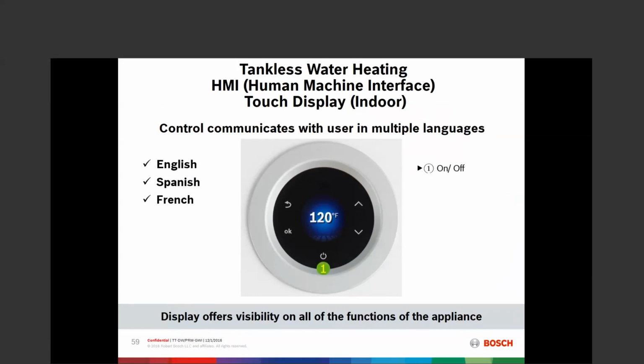Moving clockwise around from there, we have the OK. OK, most people recognize as meaning enter, accept, select, go. A return arrow, that's escape, get out, return, go back, however we want to say it. And then the carets are going to allow us to scroll set point temperature. When we're inside of the diagnostics menu, it allows the scrolling through the menu.